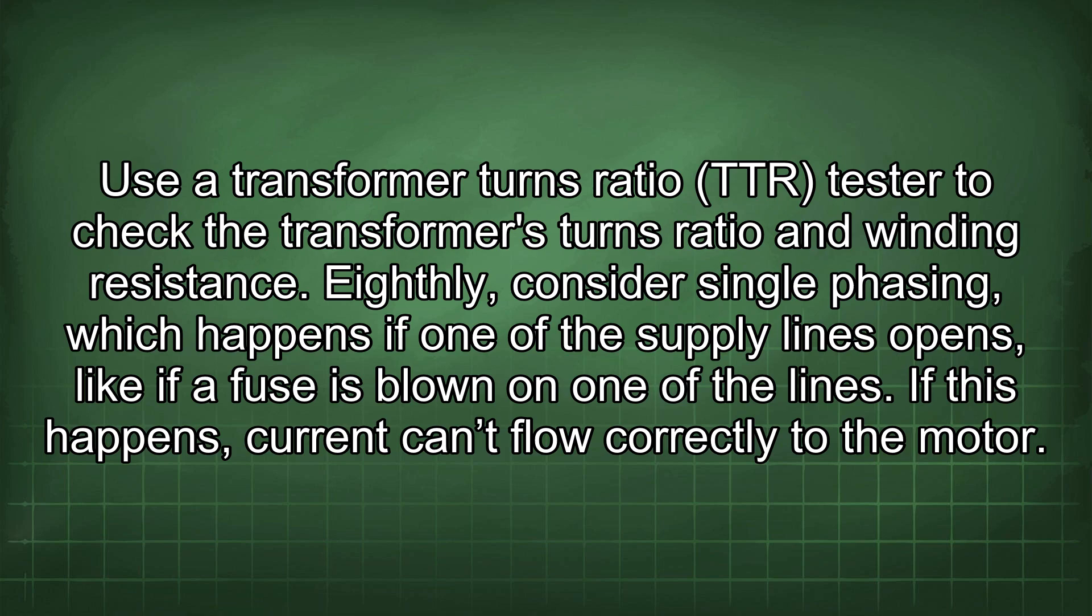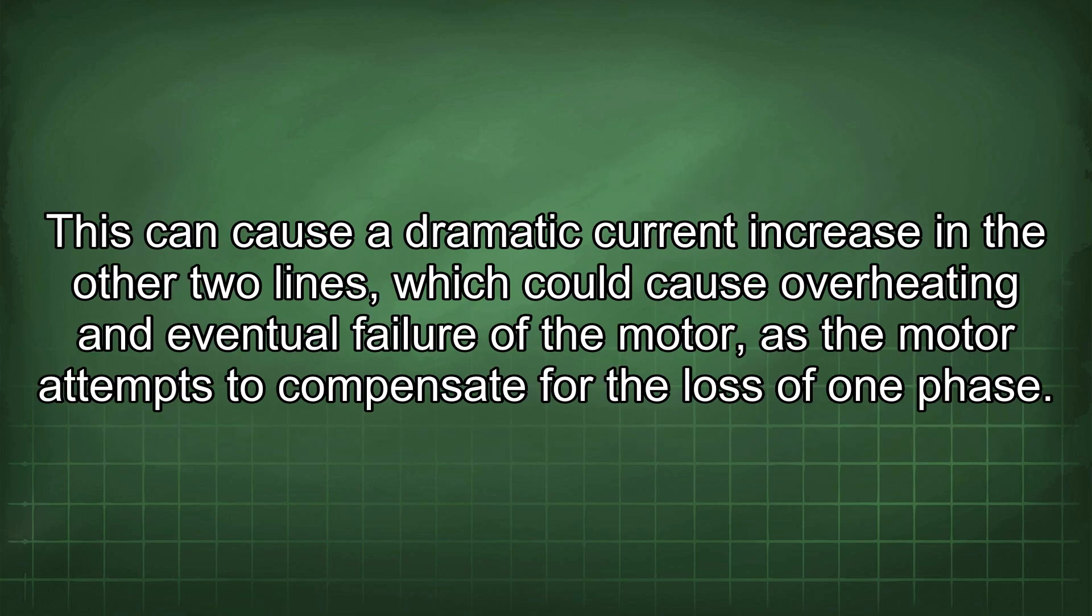Eighth, consider single phasing, which happens if one of the supply lines opens, like if a fuse is blown on one of the lines. If this happens, current can't flow correctly to the motor. This can cause a dramatic current increase in the other two lines, which could cause overheating and eventual failure of the motor as the motor attempts to compensate for the loss of one phase.